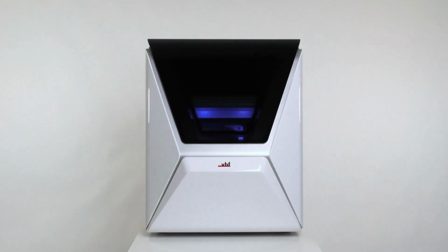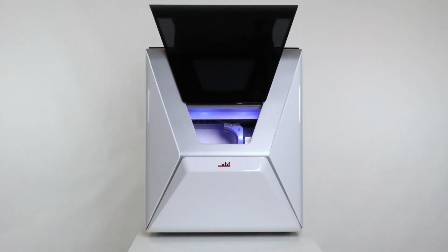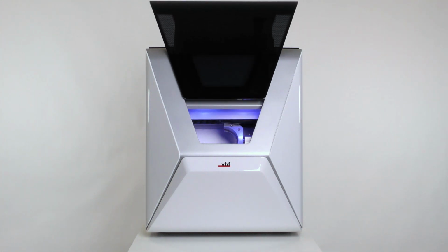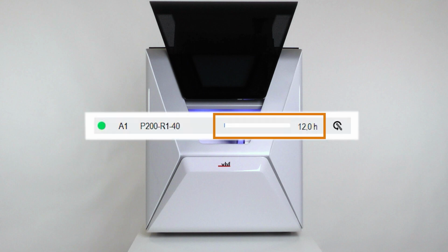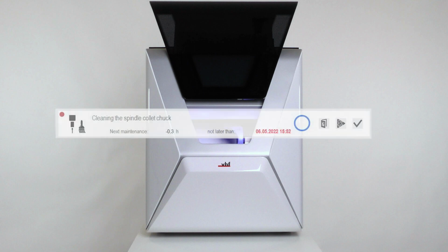At delivery, your machine is already calibrated and the accuracy has been verified. In addition, the accuracy is regularly checked during preventive maintenance by your service partner. Usually you do not have to check the accuracy of your machine yourself. In case of unsatisfactory processing results, first check the maintenance list in Dental CNC for pending tasks.